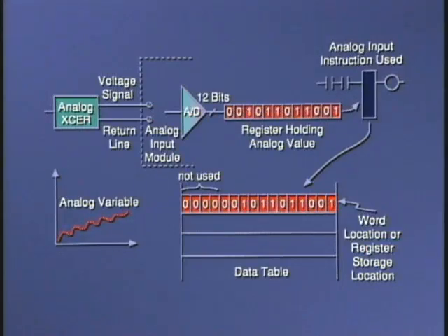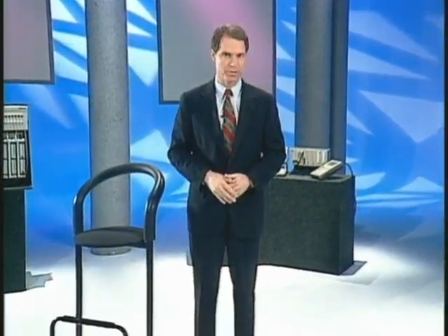The instructions used in PLCs that usually accomplish the reading of the analog inputs may be called, as we know, block transfer input instructions, analog in, block in, and it may have other names depending on the manufacturer. What's important to know is not so much the specific name of the instruction, but to understand how the data is being handled. If you know the syntax of the instruction, which is the way the instruction is represented and described in the program, and not the handling of it, you may encounter problems down the road.